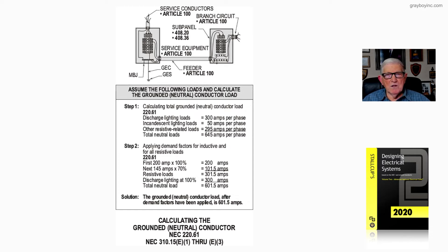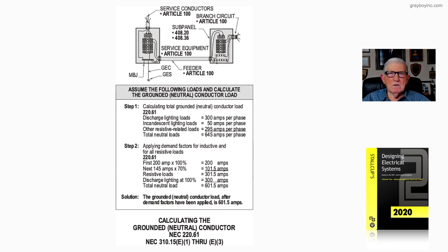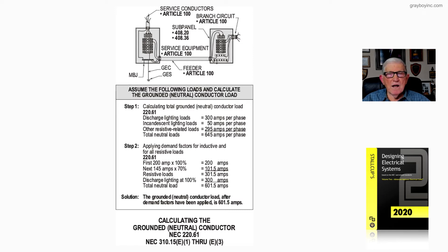When you go to 220.61, you separate the loads. Do you have inductive loads, harmonics, non-linear loads, or incandescent loads? If you have any of those loads, you divide them into the amount of amps or VA that you would have.